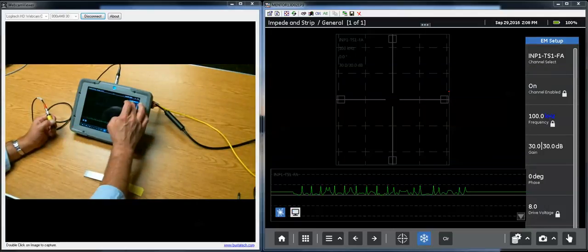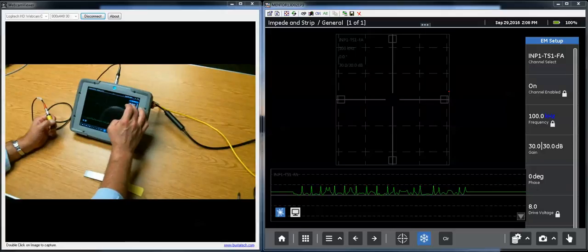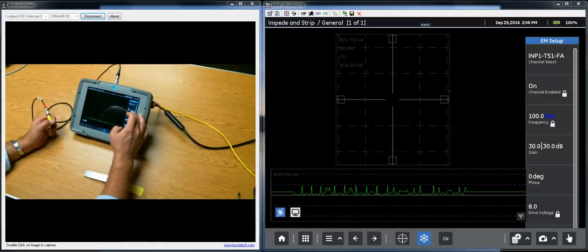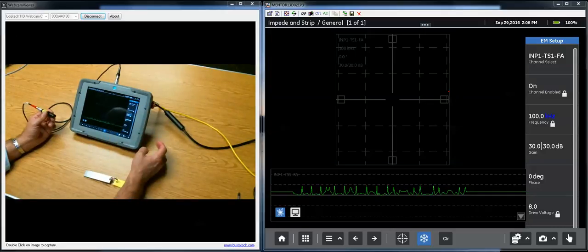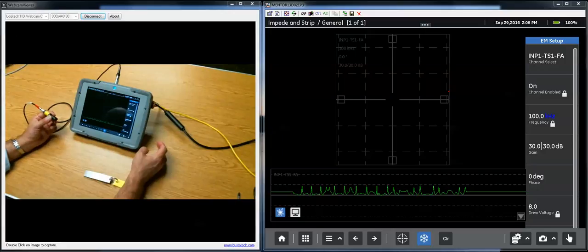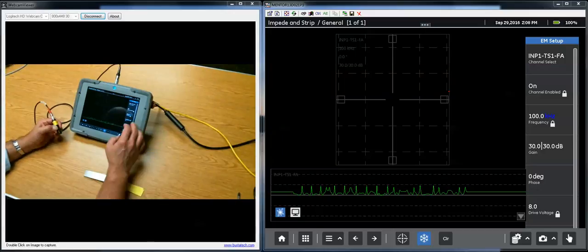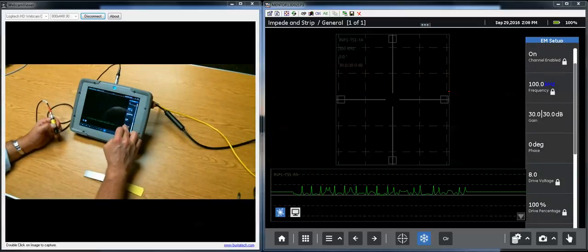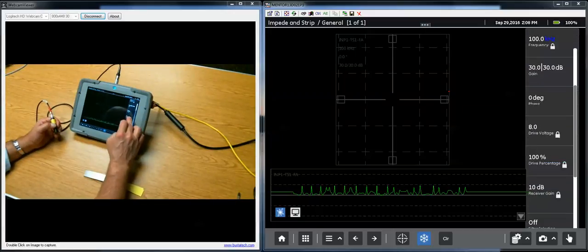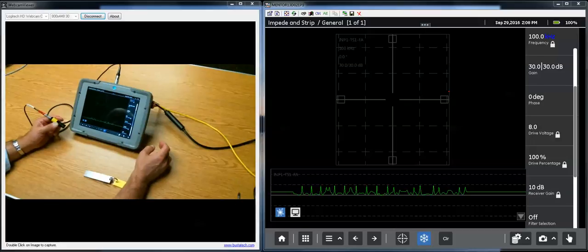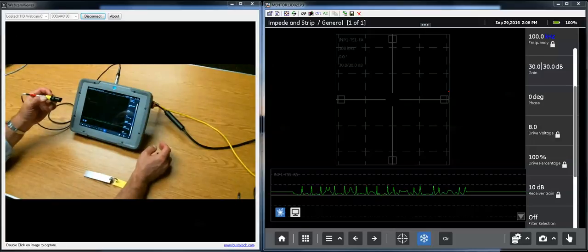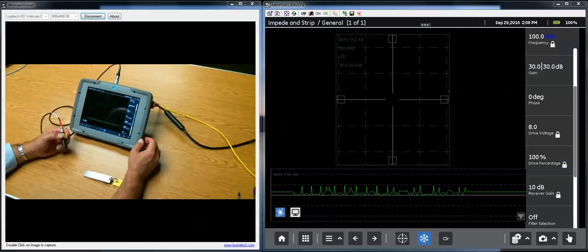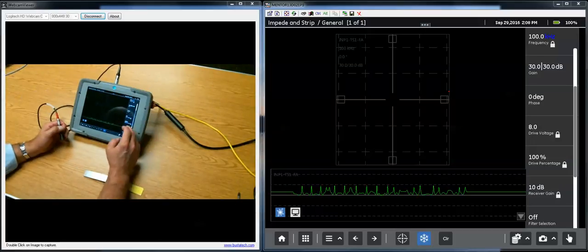On the Eddy Current menu you have channel selection. In this case we're only running one channel, the frequency that we're inducing into the probe, carrier frequency, gain, phase. Drive voltage is how much signal the generator of the instrument is putting through the coils of the probe.